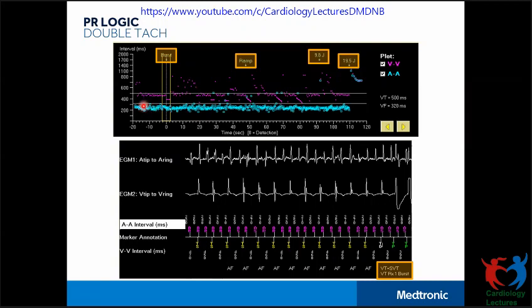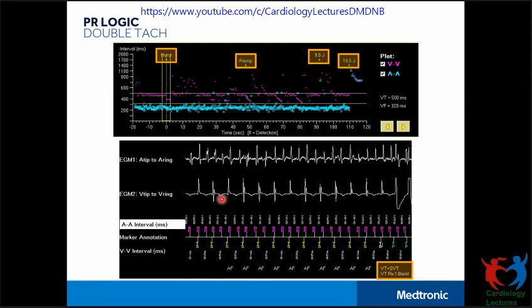In this double tachycardia plot, the atrial rate is faster than the ventricle and quite irregular, while the ventricular rate is quite regular. Comparing the association, they are completely dissociated. Looking at the EGM, atrial beats are more than ventricular beats. The device calls this 'VT plus SVT.' The device classified it as VT because the VT rate was quite regular, and in this example the device gave burst therapy, then a ramp, then two shocks, after which the arrhythmia stopped and returned to normal sinus rhythm.